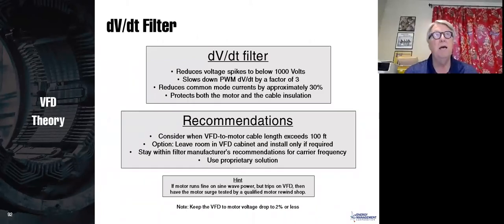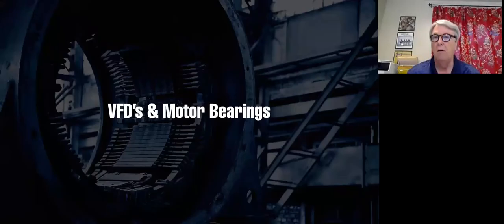So we recommend a dV/dt filter, and I showed it to you before. Anytime the motor is either not VFD rated or the cables between the motor and the drive are 100 feet or more. So again, you don't need the filter if you have a VFD rated motor and you have something like soft PWM. If you have not a VFD rated motor, I would recommend a dV/dt filter, period. Other than that, anything over 100 feet, we recommend a dV/dt filter. What it really does is prevent those voltages from going over 1,000 volts, which is the rating of the motor.